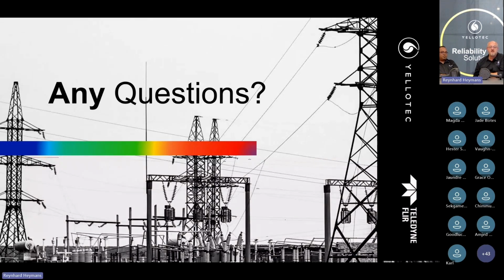So what frequencies can it detect? In this case, it can detect from 20 kilohertz going all the way up to 60 kilohertz. There is an LD unit, the Si124 LD Plus, that goes up to a higher frequency range. But for air leaks it's a specific frequency band, and for partial discharge, a different one.